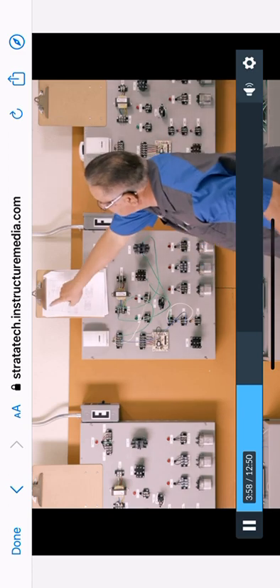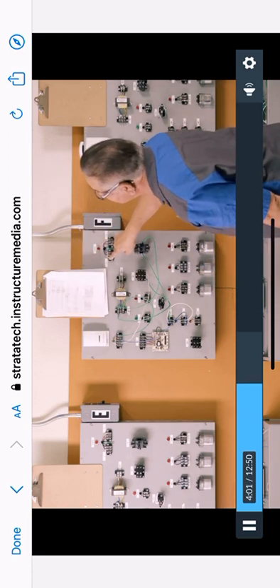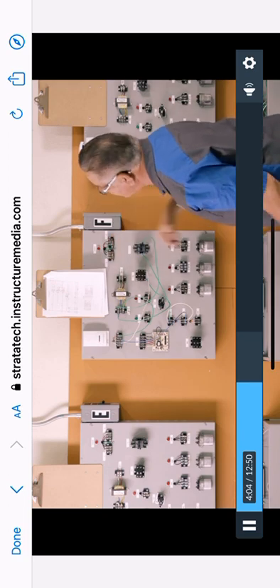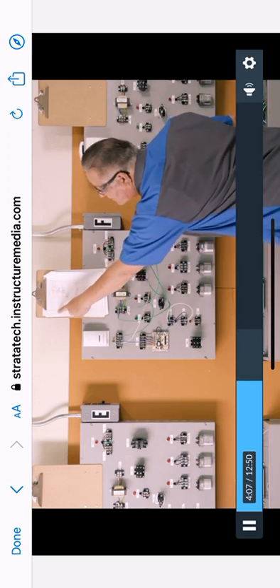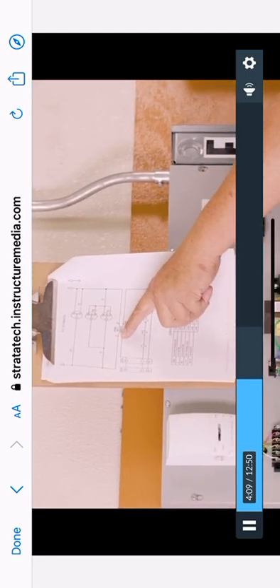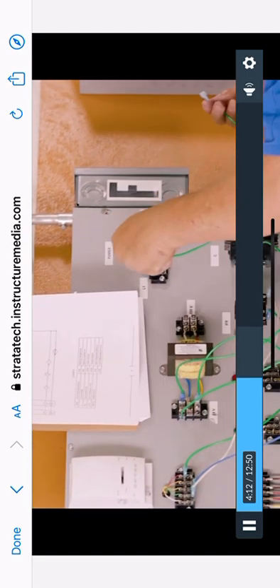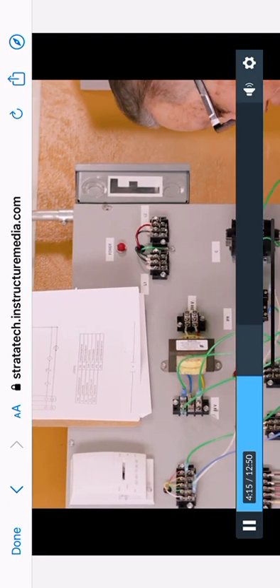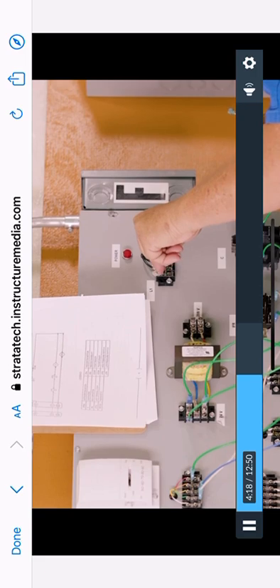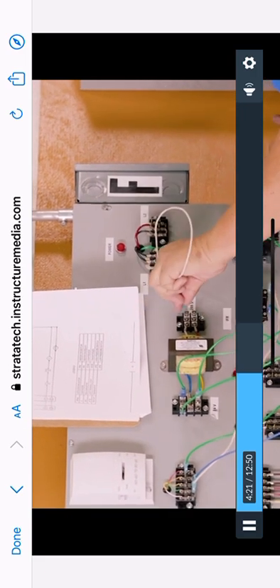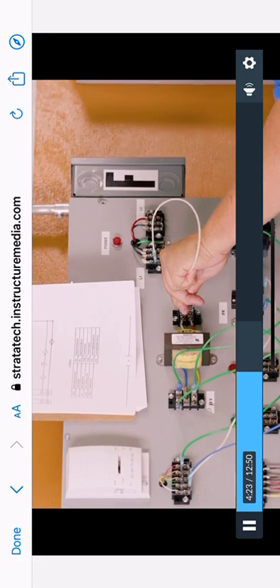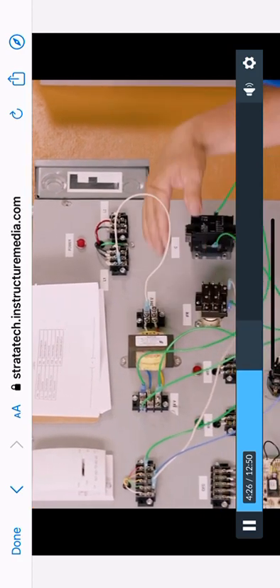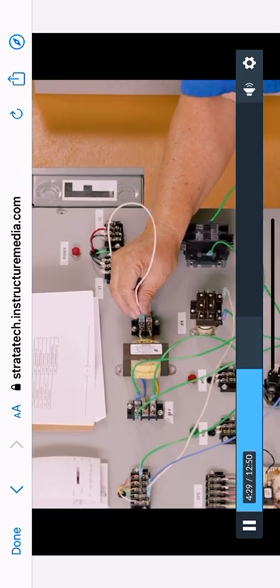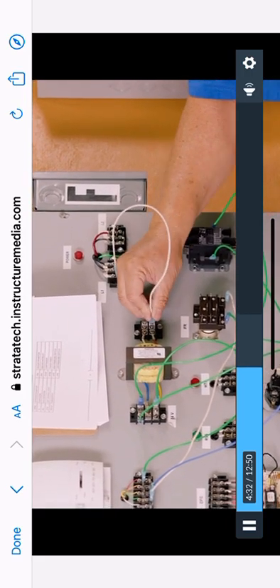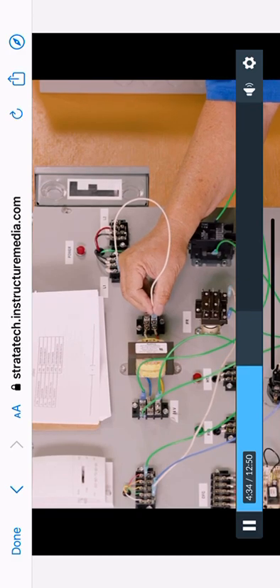So on my high voltage, I'm going to line 1. Here's line 1. First thing I want to do is hook it up to my transformer. So I'm going to hook up this line 1 right here, straight to my transformer, high side. So line 1 is going to go here. Get a shorter wire. Line 1 is going to go here. And it's going to go to one side of my transformer on the high voltage, the high side. On a transformer high side, it doesn't matter what side your wire goes on. I could put it on this white wire or I could put it on the red wire. It doesn't matter which side you put the wire on. So I'm going to go in on one side. I just hooked up my line 1.